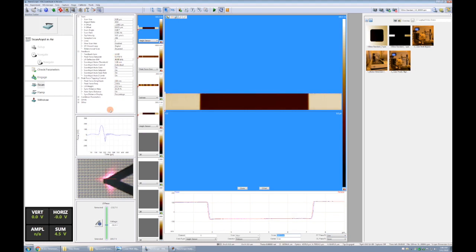Now, as I said before, now that we're scanning this box, our peak force set point has increased, and sometimes with oxides, nitrides, it can tend to run away on us a little bit. It seems pretty stable there, but yeah, see, it went up again. So what I might do is lock my auto set point off and either leave it there, or I've scanned this before at about 0.1, so I'm gonna reduce the force, and that might help save the lifetime of my tip. All right, so now it's bouncing back and forth because I'm only scanning 2 lines.